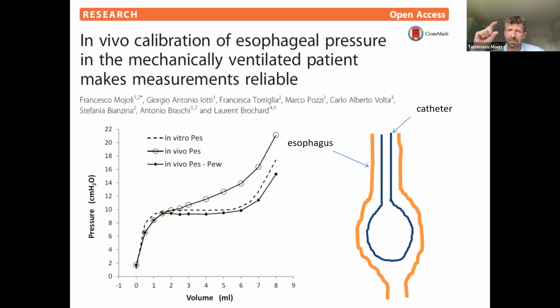So Serena is asking, delta pressure in airway pressure and esophageal pressure should be the same during the zero flow compression or inspiratory swing by the patient, correct? Yeah, this is correct. 0.8 to 1.2, you said? Yeah, this is the range. The best is when it is exactly the same, a ratio of 1, but it's considered acceptable if the ratio is in this range. Do you always try to look for 1, or if you have 1.1, you go on? I would say that if the position of the balloon is okay and you optimize the filling, you are often able to be very close to 1.